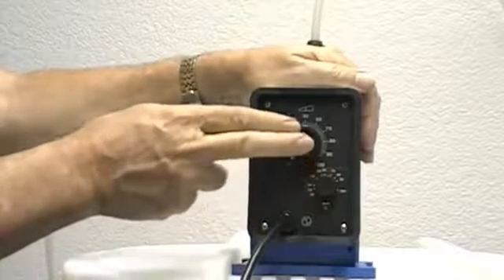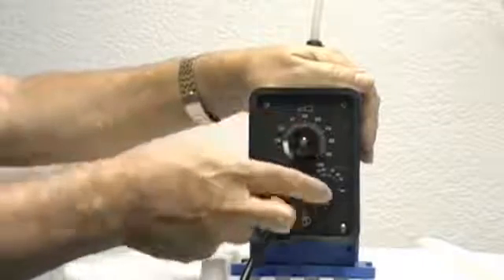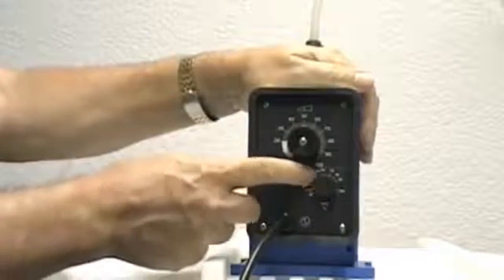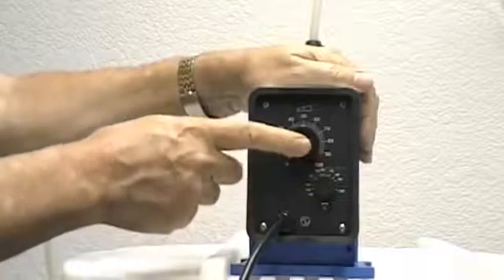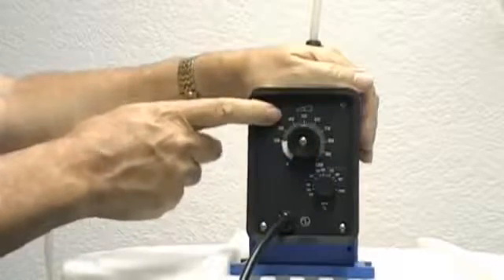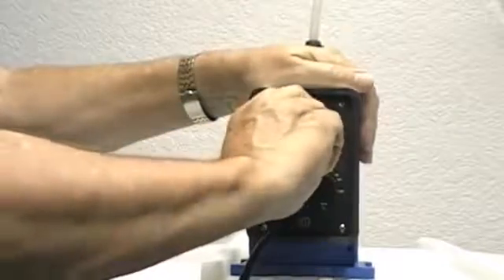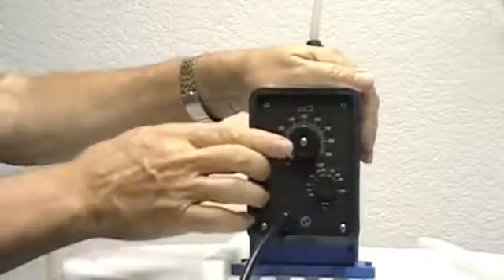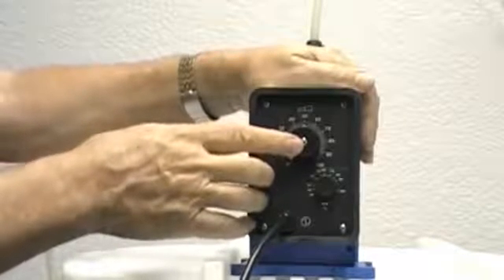As an example, for a six gallon a day pump with the stroke rate adjustment at 50%, there would be three gallons per day produced by the pump. If we adjust the stroke length to 50%, then that will reduce the flow rate to one and a half gallons per day.